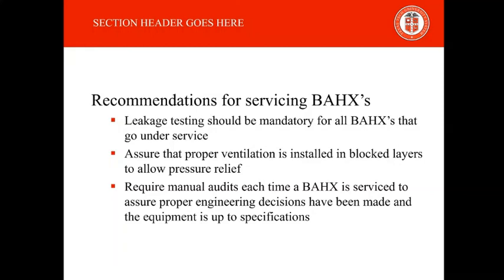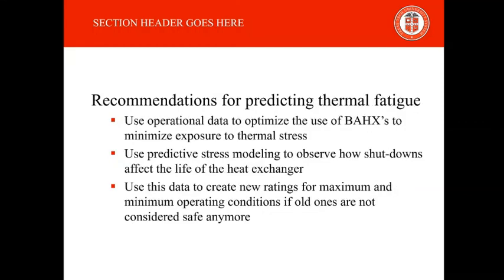Now I'll give my recommendations for predicting thermal fatigue. Recommendation number 1 is to use operational data to optimize the use of brazed aluminum heat exchangers to minimize exposure to thermal stresses. Recommendation number 2 is to use predictive stress modeling to observe how shutdowns affect the life of the heat exchanger. Recommendation number 3 is to use this data to create new ratings for maximum and minimum operating conditions if old ones are not considered safe anymore.